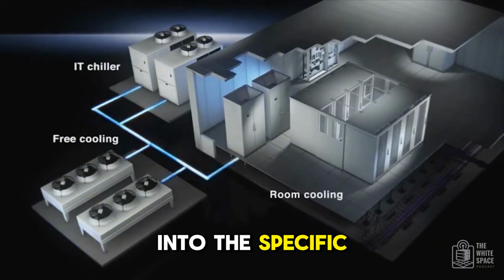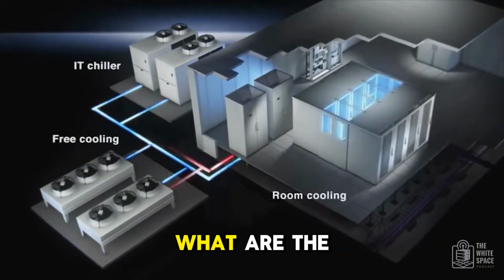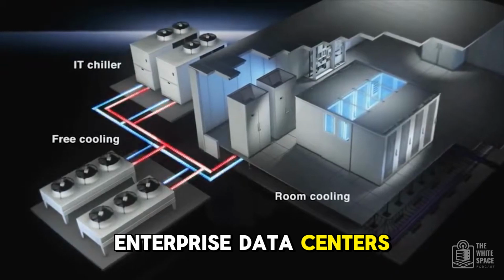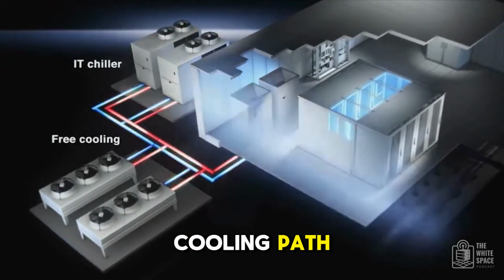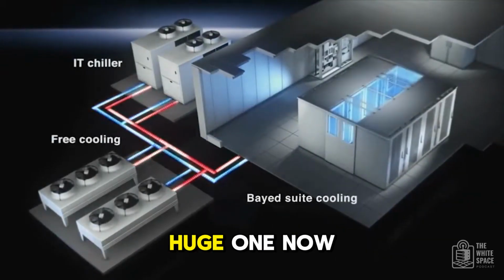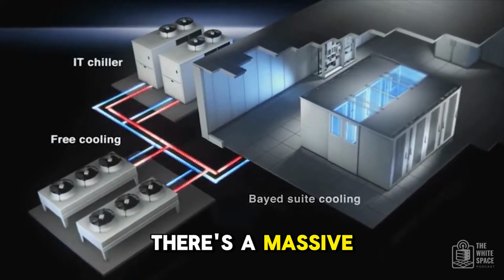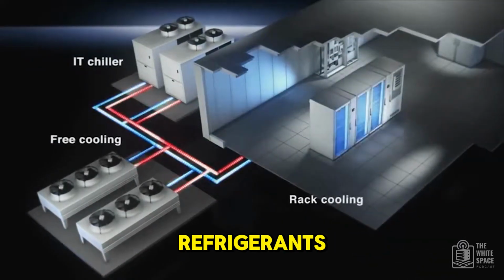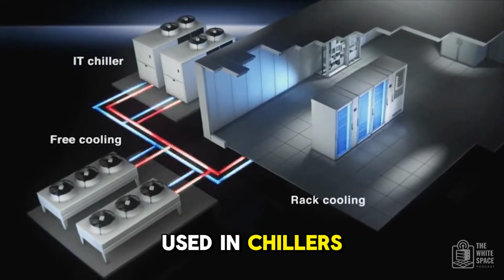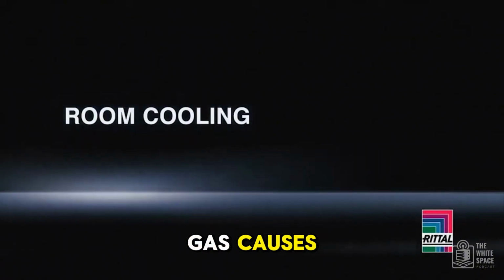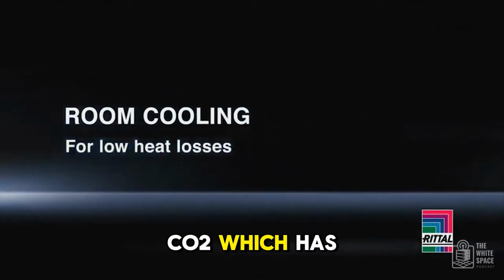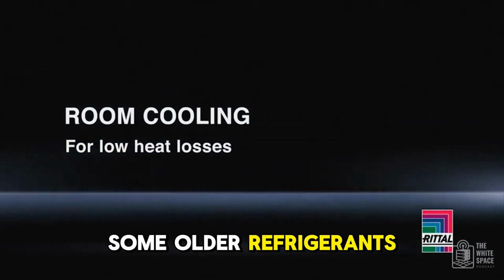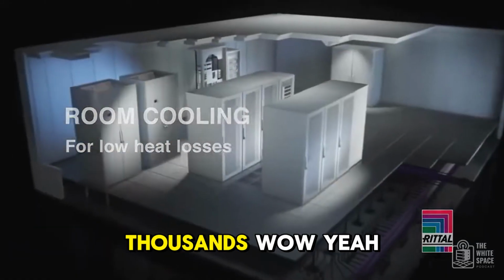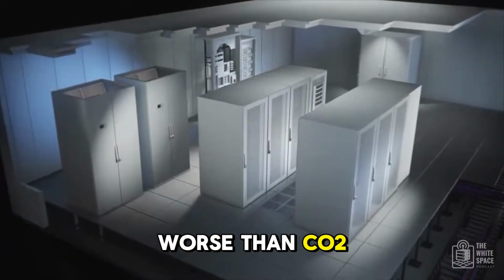So we've dug into the specific technologies, but stepping back, what are the bigger picture things enterprise data centers need to weigh up when choosing their cooling path? Sustainability and regulation seem like a huge one now. Oh, absolutely critical. There's a massive global push towards refrigerants, the cooling fluids used in chillers and some AC systems, that have a low global warming potential, or GWP. GWP just measures how much warming a gas causes compared to carbon dioxide, CO2, which has a GWP of 1. Some older refrigerants have GWPs in the thousands. Thousands, wow. Yeah, thousands of times worse than CO2 for the climate.